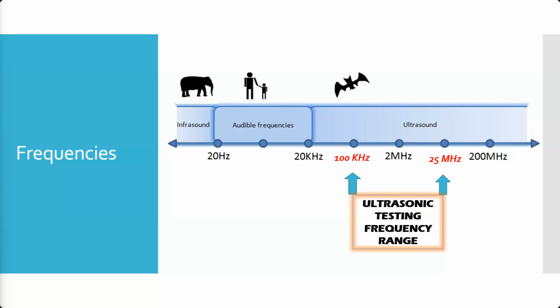With ultrasound, we're usually going to be somewhere in the 50 to 100 kilohertz up to about 25 megahertz range. That's what our testers are going to be running, and you're going to have to set that frequency as part of your testing process. Different probes are designed to work with different frequencies. So some testers allow you to set it, others don't.